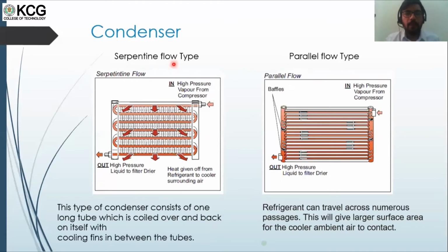So now we see the condenser. There are two types of condenser widely used. The earlier ones which were used were the serpentine flow type. So what will happen? The refrigerant will enter at high pressure and temperature. It will get cooled down, as you can see, as it flows through the pipes. So this area will be at high temperature and this will be at low temperature. So it will have an unequal heating.